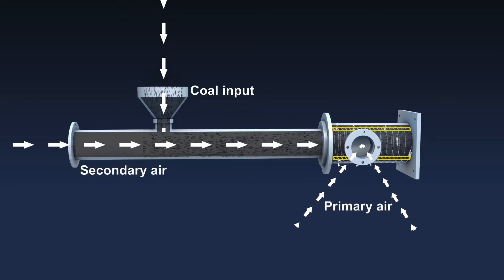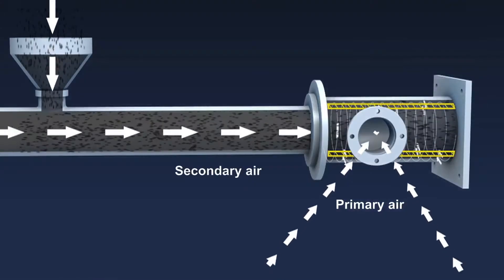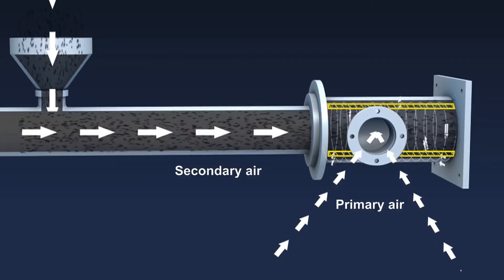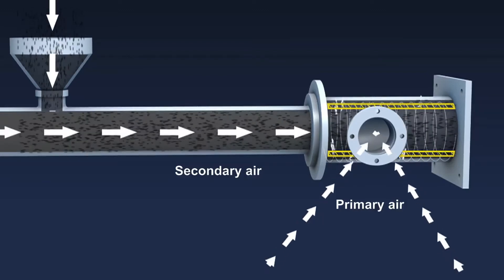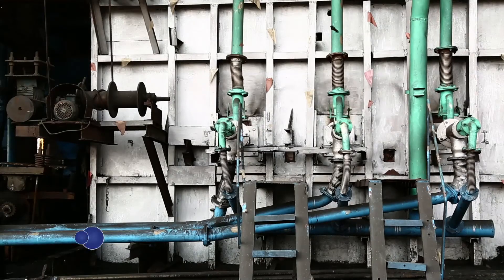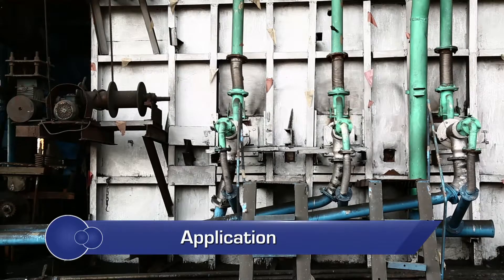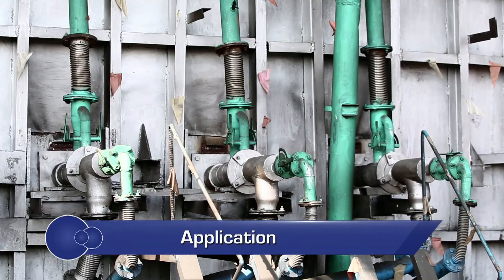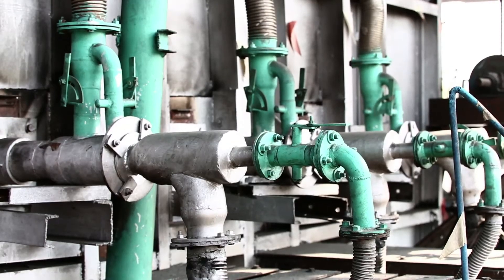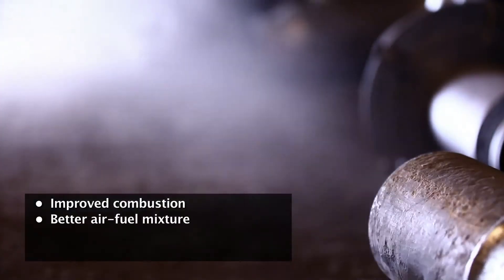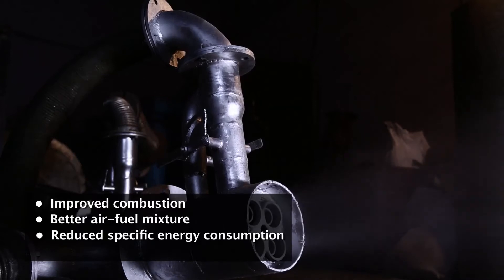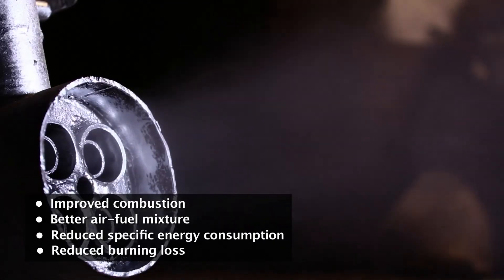The turbulence caused due to the rotation of the air fuel mixture, generated by the vanes swirl generator, results in proper air fuel mixing and better combustion of fuel. Swirl burners can be used for any capacities of furnaces fired by pulverized coal and have the following advantages over a conventional furnace: improved combustion, better air fuel mixture, reduced specific energy consumption and reduced burning losses.